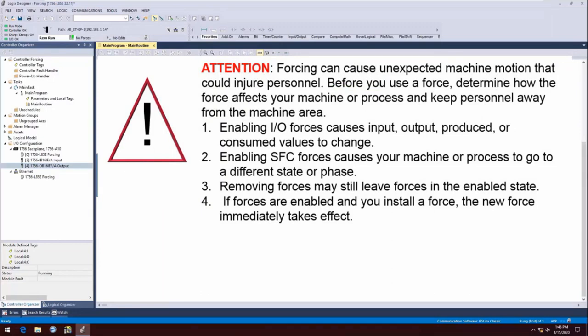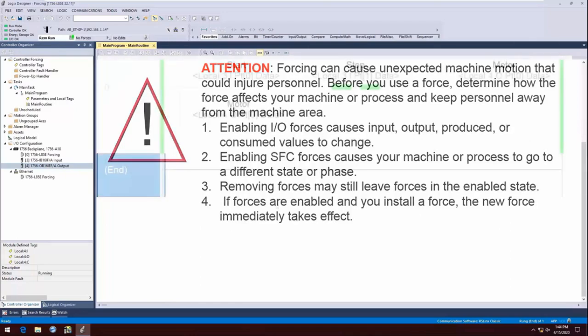Before you use a force, determine how the force affects your machine or process and keep personnel away from the machine area. Enabling SFC forces causes your machine or process to go to a different state or phase. Removing forces may still leave forces in effect if forces are enabled. If forces are enabled and you install a force, the new force immediately takes effect.